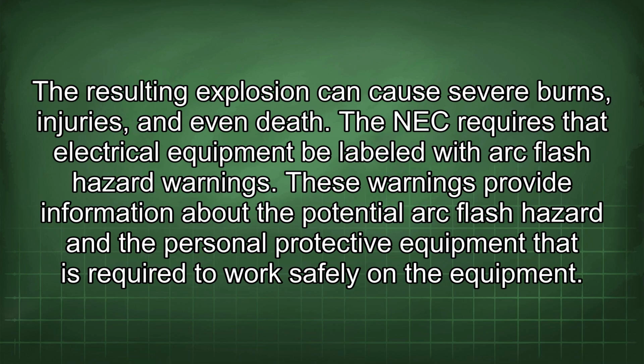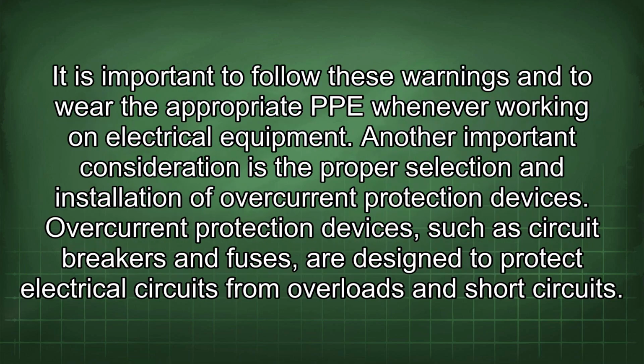The NEC requires that electrical equipment be labeled with arc flash hazard warnings. These warnings provide information about the potential arc flash hazard and the personal protective equipment that is required to work safely on the equipment. It is important to follow these warnings and to wear the appropriate PPE whenever working on electrical equipment. Another important consideration is the proper selection and installation of overcurrent protection devices.